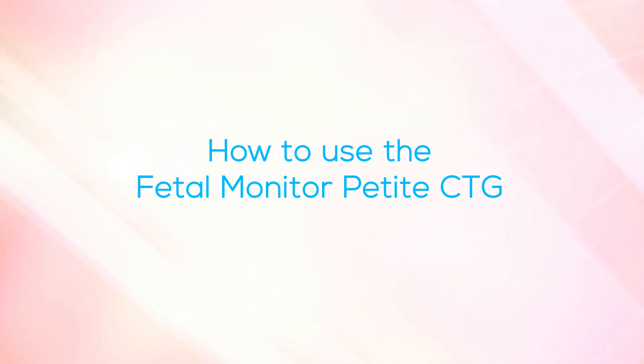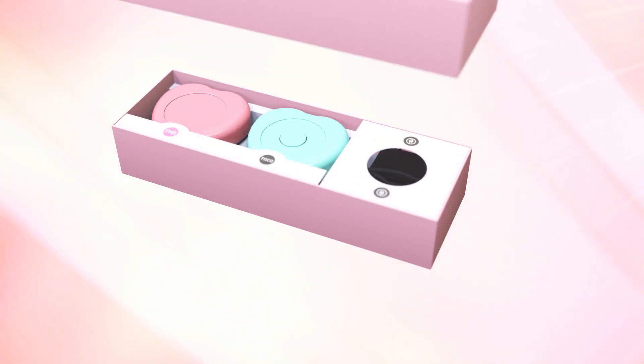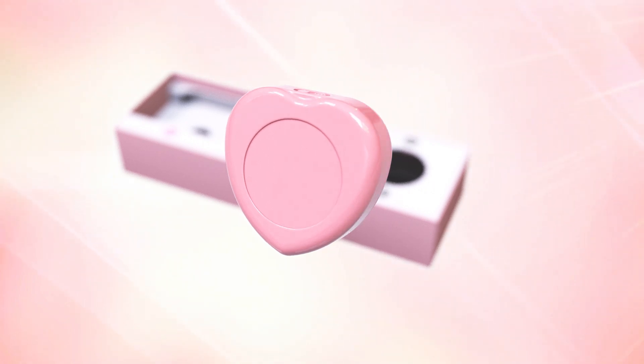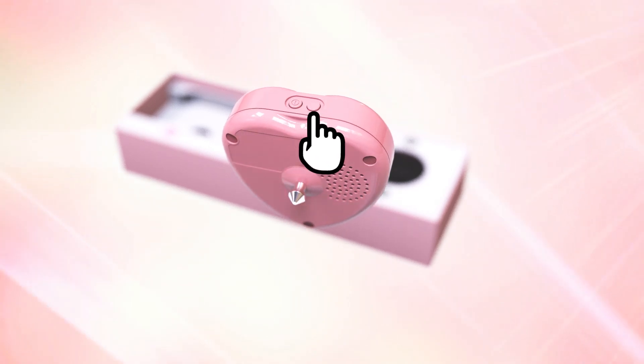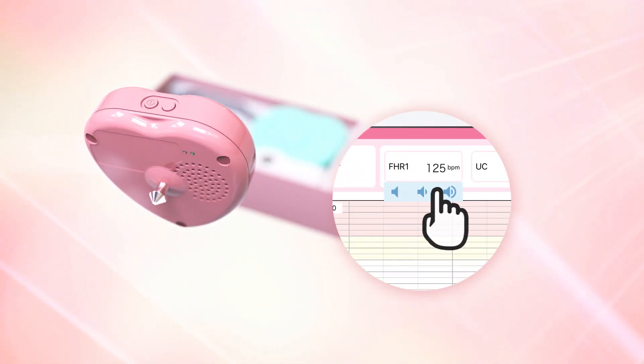How to use the Fetal Monitor Petite CTG. This is the transducer for the fetal heartbeat. The sound of the heartbeat is heard from the speaker. It has a power button and a volume button at the side. Volume adjustment can also be done on the application.